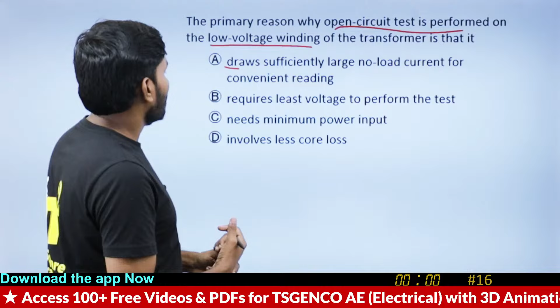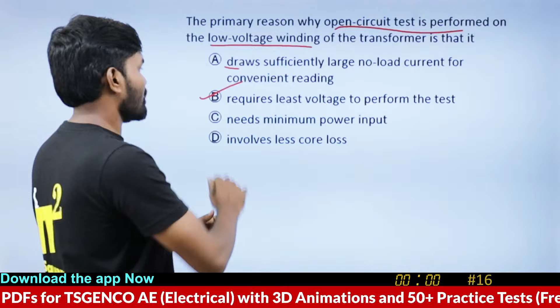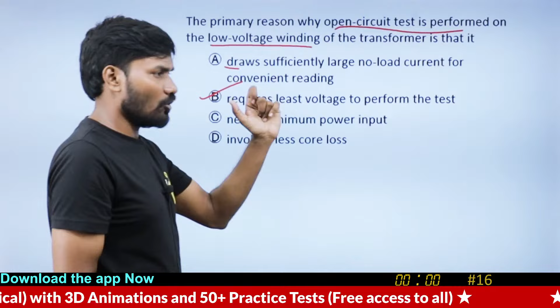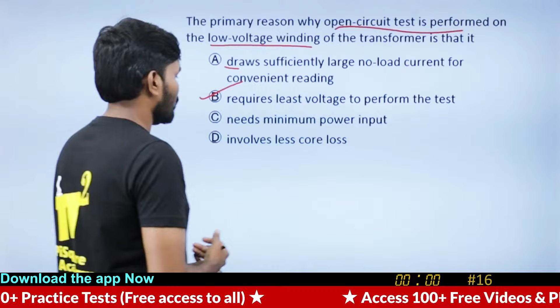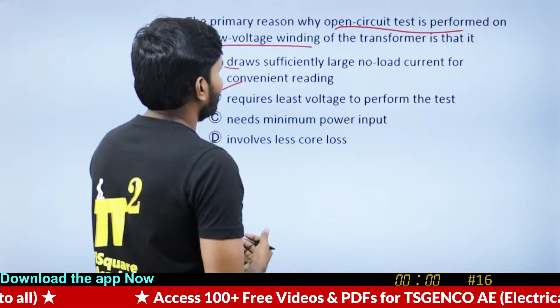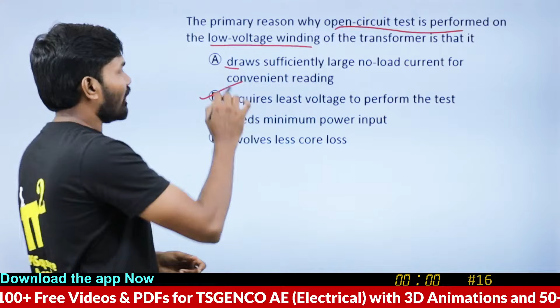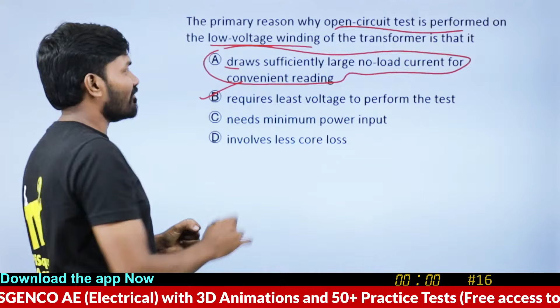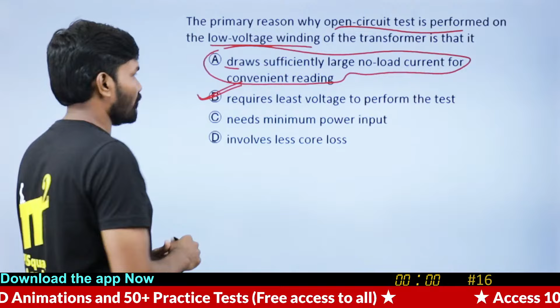The real answer is that it requires the least voltage to perform the test, not about the power - power remains the same whether you connect on the primary side or the low voltage or high voltage side. No-load power is pretty much the same, so there's no difference in power, and if power is the same, core loss is also the same. Textbooks often say it's about drawing large no-load current for convenient reading, but that's not the primary reason. The prime reason is the least voltage requirement - you can check that video for the practical insights.